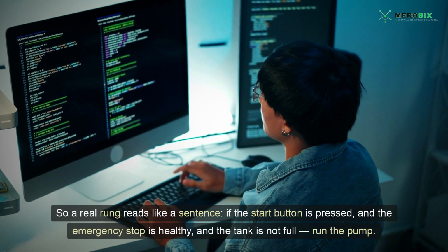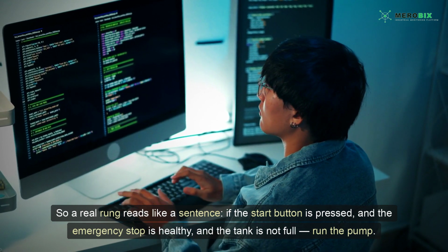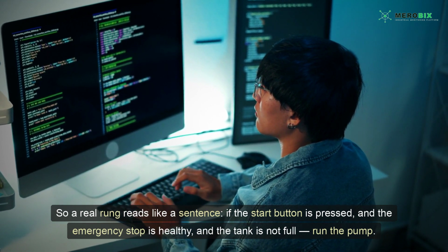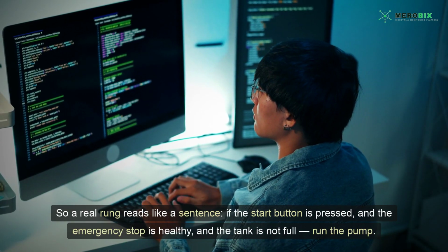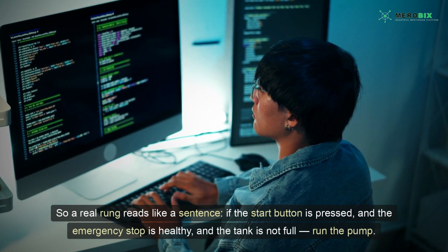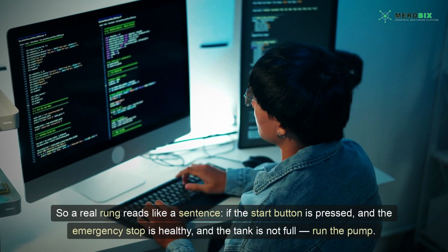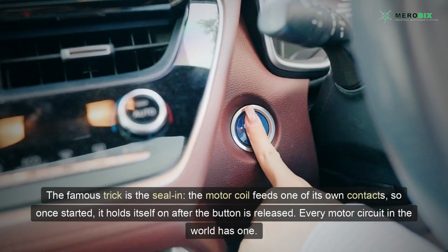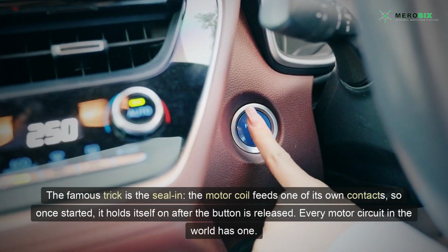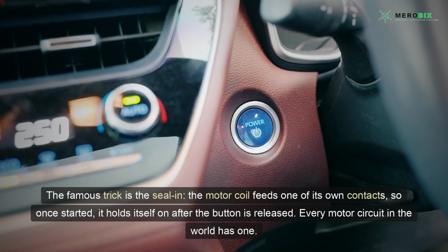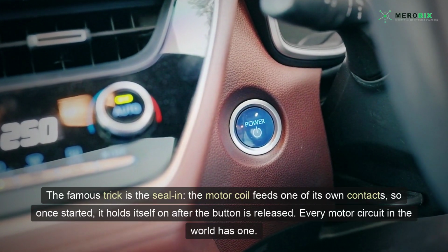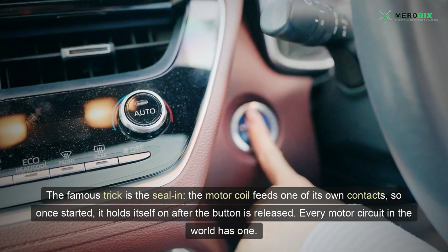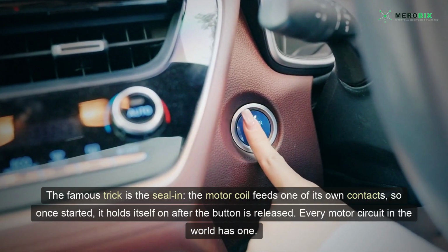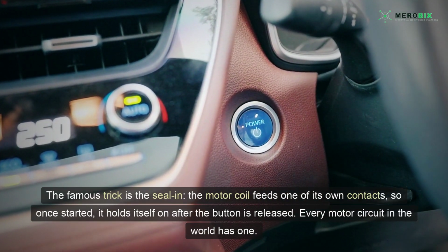So a real rung reads like a sentence. If the start button is pressed, and the emergency stop is healthy, and the tank is not full, run the pump. The famous trick is the seal in. The motor coil feeds one of its own contacts, so once started, it holds itself on after the button is released. Every motor circuit in the world has one.